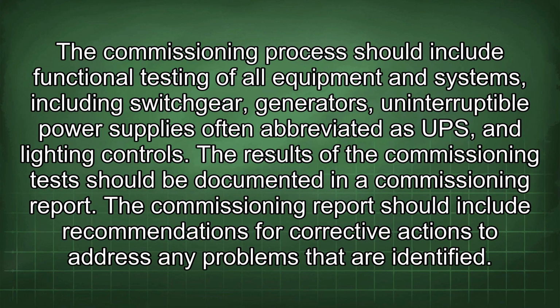The commissioning process should include functional testing of all equipment and systems, including switchgear, generators, uninterruptible power supplies, often abbreviated as UPS, and lighting controls. The results of the commissioning tests should be documented in a commissioning report. A commissioning report should include recommendations for corrective actions to address any problems that are identified.